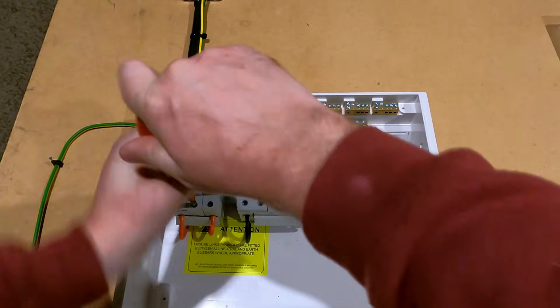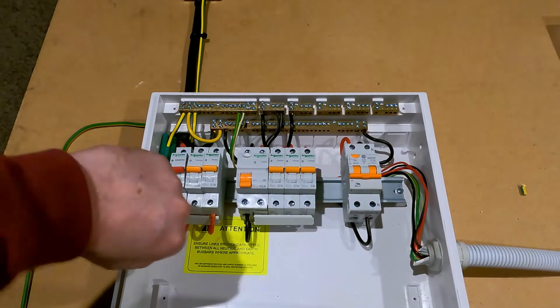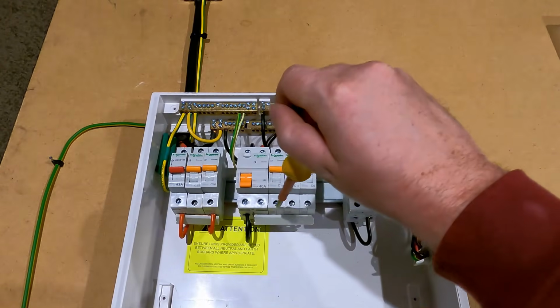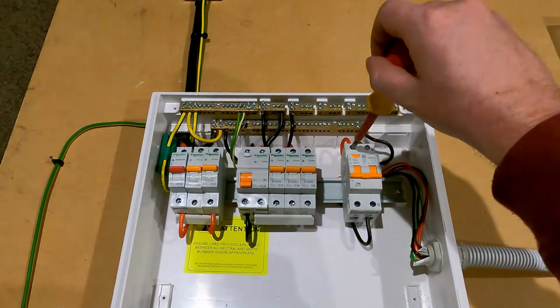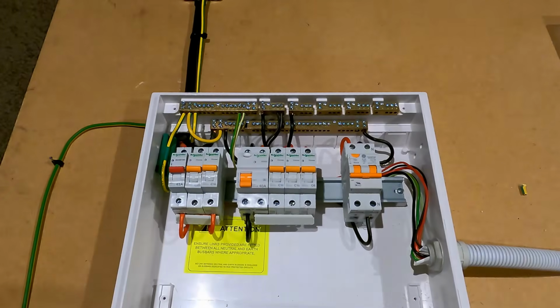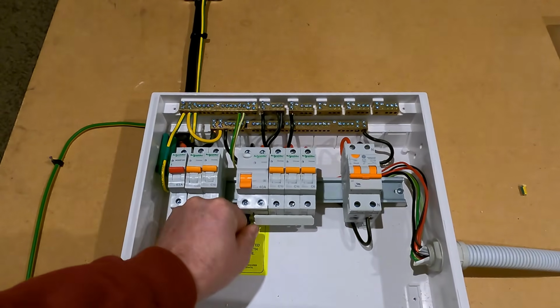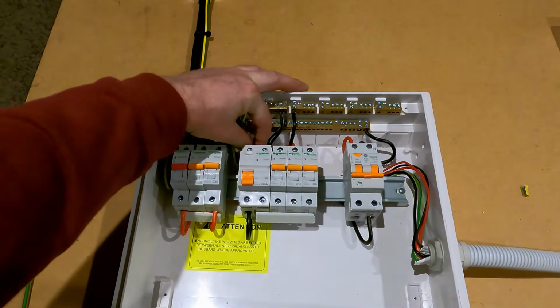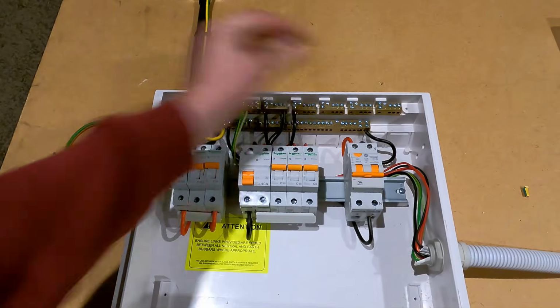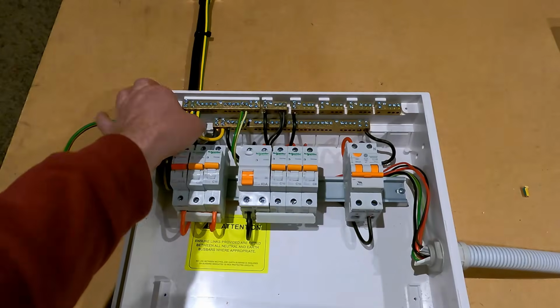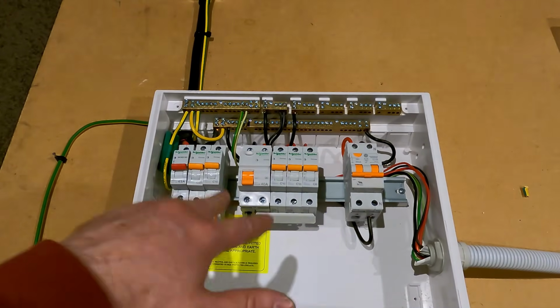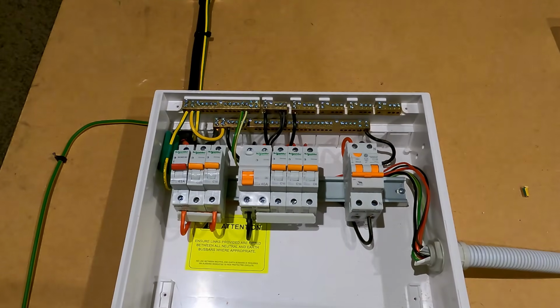Nice. Looks like we've got a loose terminal here. So tighten that one up. Then we get our big flat head and crank it up a wee bit. Just go through the whole lot. Cool, they're perfect. And then you can also go around and do a quick pull test on all of the conductors. Make sure that nothing's coming loose or falling out. And we're good. I've come across so many of these terminals that people have forgotten to tighten up. They've created hot spots on the circuit breakers over time and melted and welded things together, which could have caused fires. So make sure you do that.